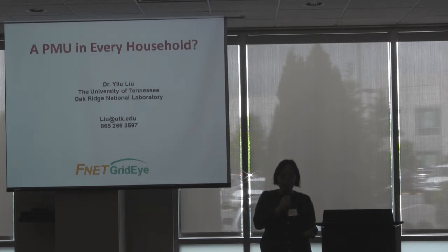He happened to have developed a single-phase PMU algorithm, which calculates single-phase phasors. Remember, three-phase is a spatial vector that's rotating in space, and it's reasonably easier to do the phasor in three-phase, but it's actually a little twisted for single-phase. So he had already developed the single-phase algorithm for calculating voltage, or current, doesn't matter, phasors. All I needed to do was basically use it. He also had developed a robust technology to calculate the frequency out of those single-phase phasors. Those were made for under-frequency relay application.